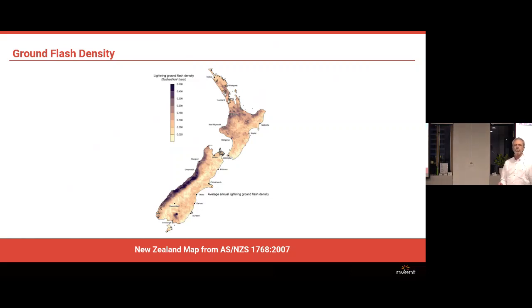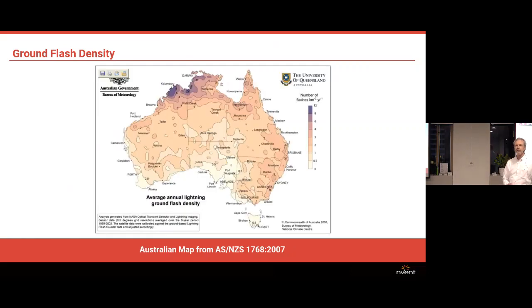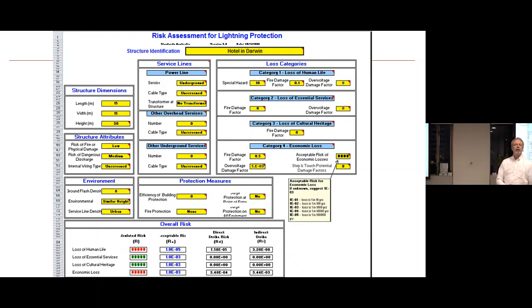If we go to the Australian map, which is also in the same standard, it's got similar colours, but the top of their scale is 12 flashes per square kilometre per year. So it's a lot bigger, 20 times the scale of the New Zealand one. So don't look at the two maps and think that they are comparable. Our top density is only at the top of their bottom mark on their scale. So not so much lightning here. I'll go back to that.